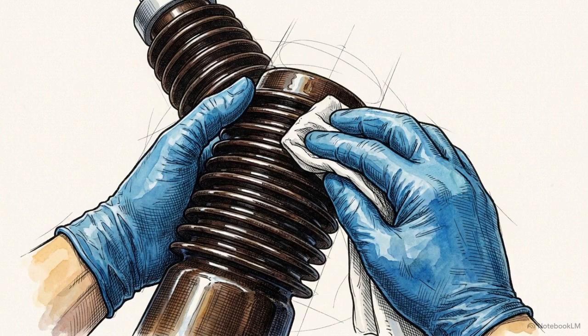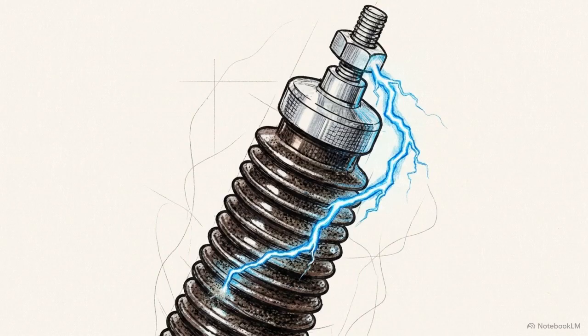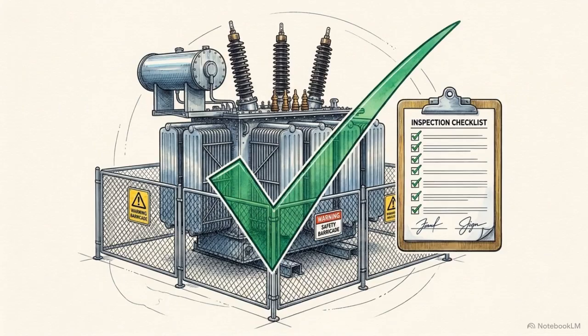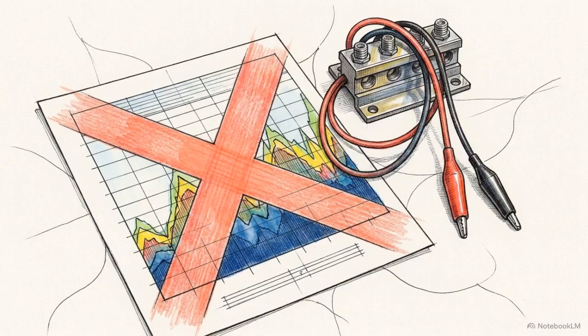Every bushing must be thoroughly wiped down to remove dust, moisture, and conductive contamination. If left on the ceramic or polymer surfaces, this residue creates a path to ground that will cause flashovers during 5 and 10 kilovolt testing. That pristine, mathematically verified as-found safety state is the only valid starting point. Any data collected from a compromised setup is useless for subsequent diagnostics.